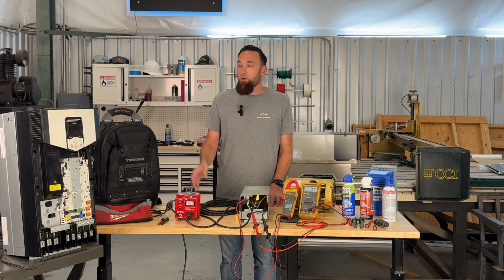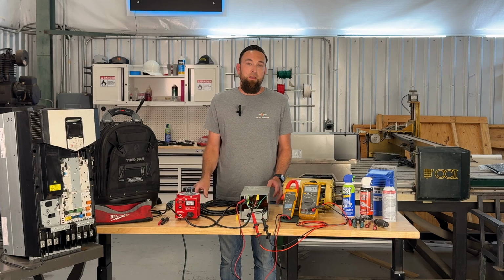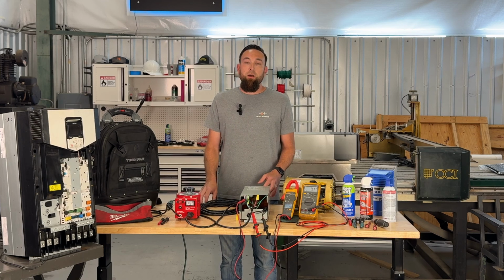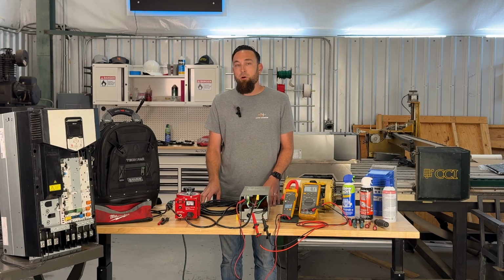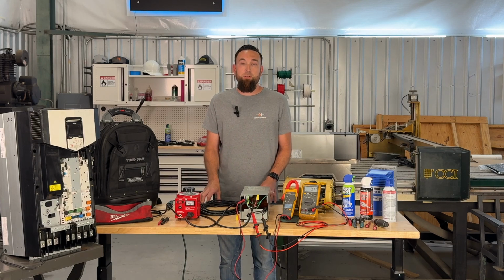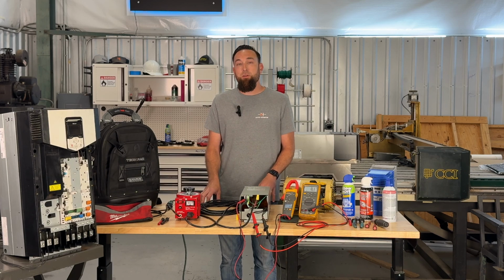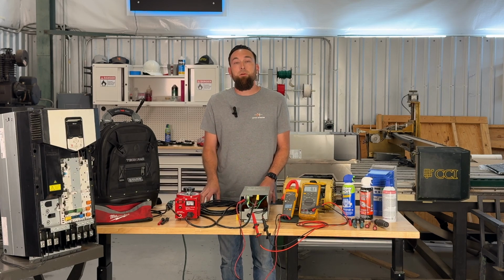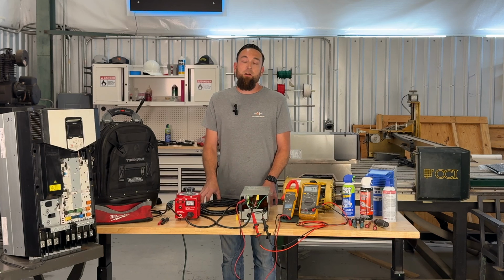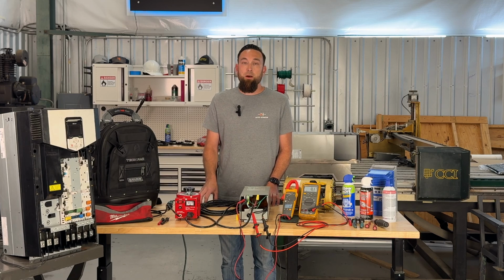Electrolytic capacitors are in the center of any VFD, and these capacitors actually have a shelf life. You can't let them sit for too long without having voltage applied to them. Whenever we apply voltage, there's actually a reaction that happens inside that rebuilds the oxide layers, and the oxide layers are essential to preventing internal arcing, which can lead to pressure buildup and capacitor explosion.